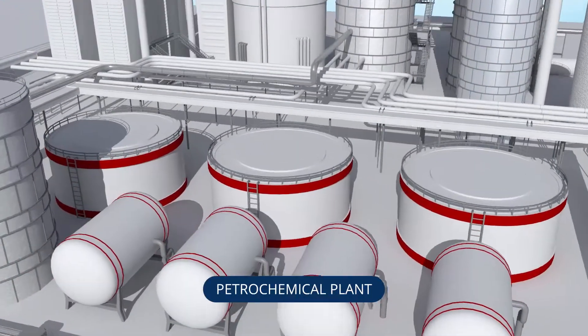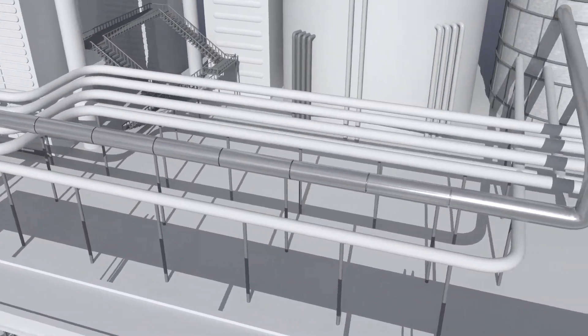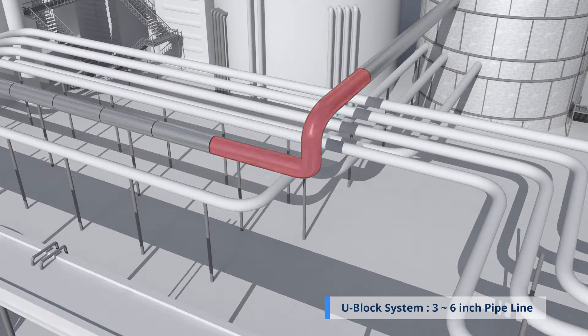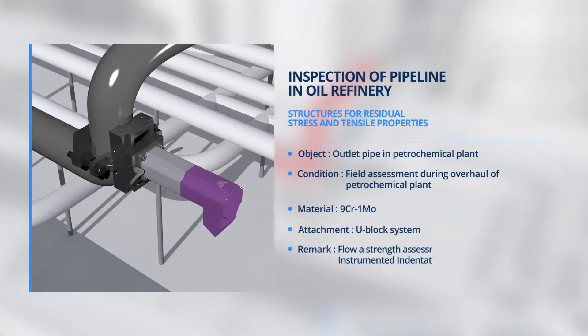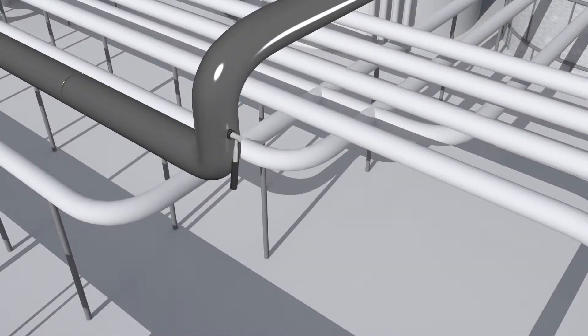The second case to be introduced is a petrochemical plant, and the attachment used is the U-block system. Using a U-shaped block, this attachment is applicable to 3 to 6 inch pipe. The test object is a pipe at a petrochemical plant, and the test is intended to evaluate the deterioration of the pipe over time. It is also applicable to evaluating residual stress on welding pipe. After surface profile is achieved, the tester is attached to the test object using the U-block system.